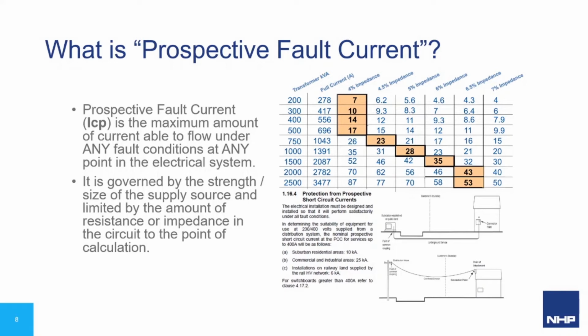The level of the current is dependent on the supply strength and any latent impedance in the system up to the point of the assembly. The prospective fault level in our electrical system is expressed in thousands of amps, usually represented by the symbol kA. The prospective fault level at any point in the system can vary with the level of resistance or impedance in the circuit from the source to the calculated point. We always go for the worst case scenario, which is the three-phase fault. This needs to be defined before we can start designing our switchboard.